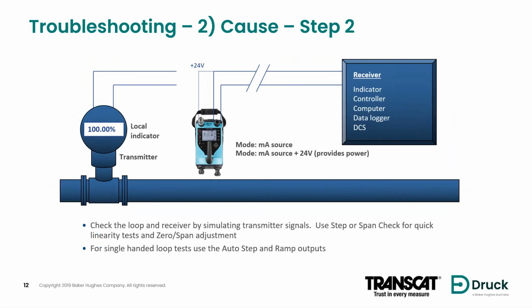And then finally, we can isolate the transmitter from the controls and again use the portable pressure calibrator to check the receiver by simulating the transmitter signal. Most portable calibrators, certainly ours does, have built-in process automation functions, so you can not only simulate that, you can enter the exact value of current or milliamps that you want to inject into the controls, or you can set up automated processes like step checks, span checks, or zero to span ramps for checking the full range of the input to the receiver.